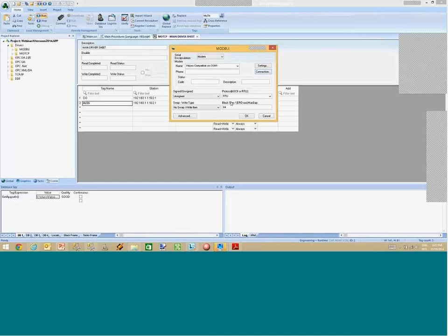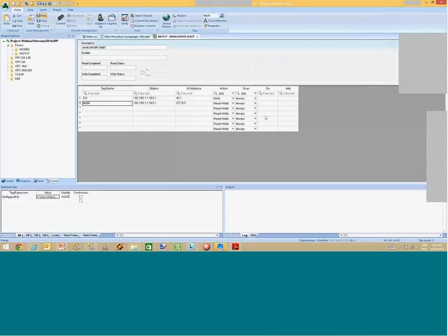But if you have to send specific AT commands to the modem, we would need to customize the driver or create another driver specifically to send AT commands to the device. Or if you configure the modem on the operating system, you can use the operating system interface itself to configure the AT commands you want to send to the modem. We have a few drivers that are specifically to initiate a communication, sending some specific AT commands to modems, but the Modbus driver uses whatever configuration you did when you installed the modem on the operating system level.